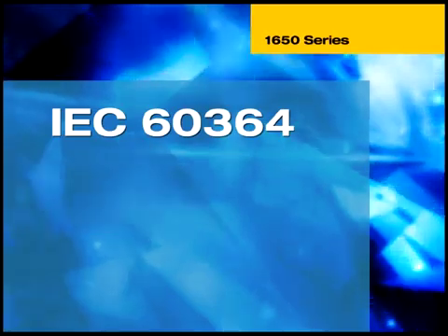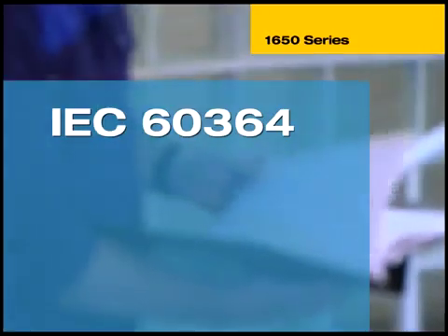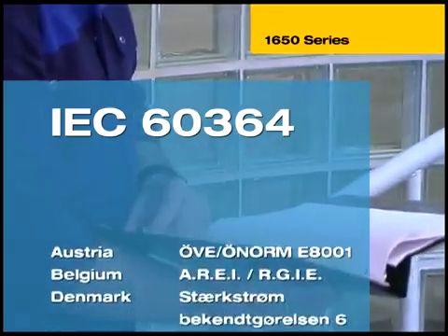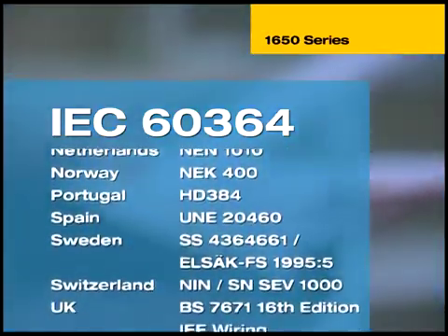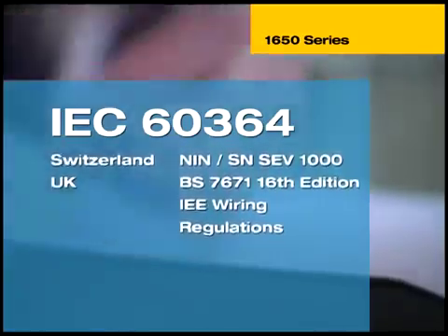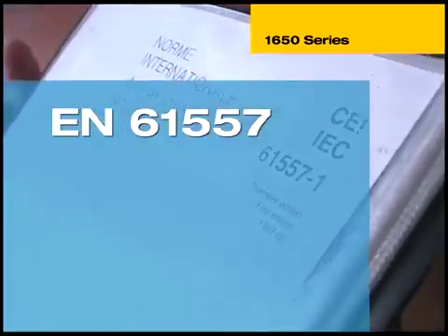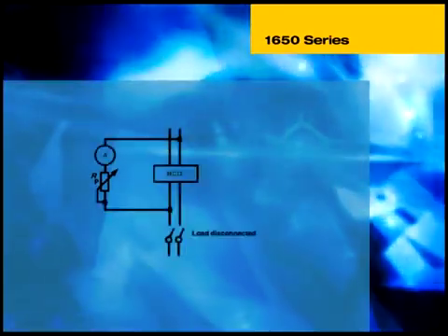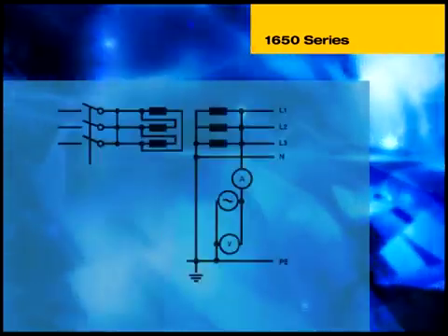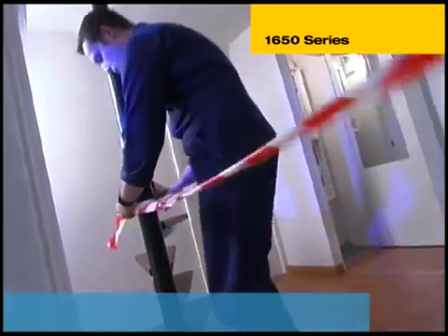Many electrical contractors and engineers may already be familiar with IEC 60364, the international norm that specifies the requirements for fixed electrical installations in buildings and describes the tests to verify conformity. IEC 60364 is the base guidance document for installation testing practice from which local standards in Europe are developed. This video is not intended to replace or supersede these recognised standards, but to demonstrate how to use the Fluke Multifunction Installation Tester to get the job done thoroughly, safely and effectively. The 1650 Series fully complies with EN 61557, the European norm covering the requirements for test equipment used in installation testing. Note that some tests are not shown in this video. If in any doubt, consult the appropriate standards publication. Please remember that only with the appropriate experience and training, safe clothing and the right test tools is a person considered competent to test installations to IEC 60364.